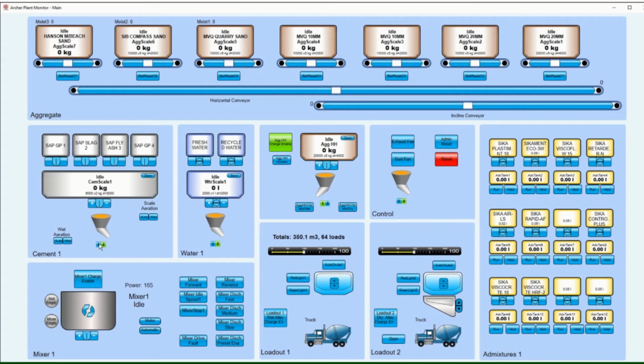Finally, you can have turn heads or swivel chutes, diverters, or flop chutes looking like the one that I'm showing here. The graphic will animate to show relative position, but more precisely, the number of buttons will highlight accordingly. The number of buttons on the control is configured to match the number of positions of the plant device. Click on a numbered button to set the device into motion and position it. If the left and right buttons are configured, click and hold to rotate the device. Release your click to stop the device.